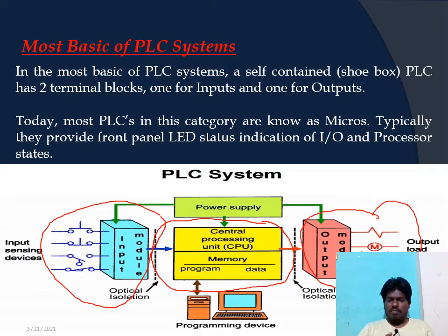But the programming device here requires communicating with the PLC through some communication channel. In this device we write the program because there is compatible software. For example, if we are using an Allen Bradley MicroLogix 1400 PLC, then it will utilize RSLogix 500. In that particular software we can write the logic and download it into the program memory, so it will be stored in the program memory.